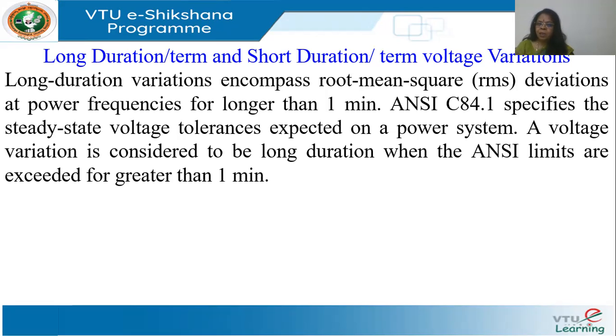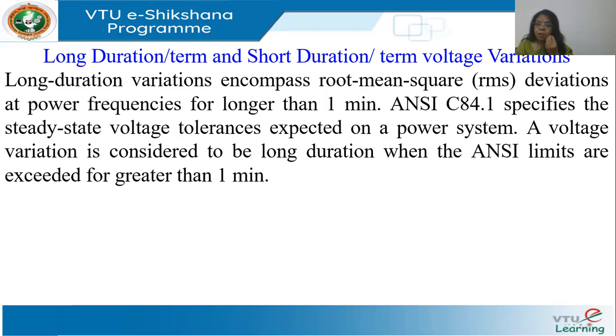Based on standards, the utility gives a tolerance band — it will provide voltage within plus or minus x percent of nominal. If the utility supplies voltage within that bracket, it is not at fault. But some equipment is very sensitive and cannot afford those deviations; the customer must then invest in a high-quality source like an uninterruptible power supply (UPS) or its own supply source.